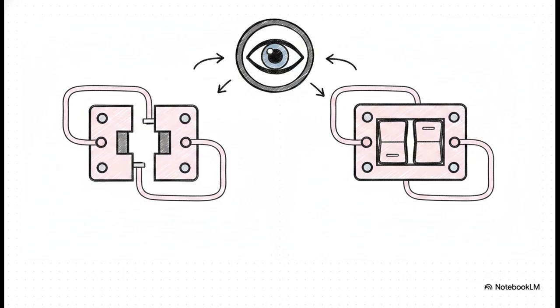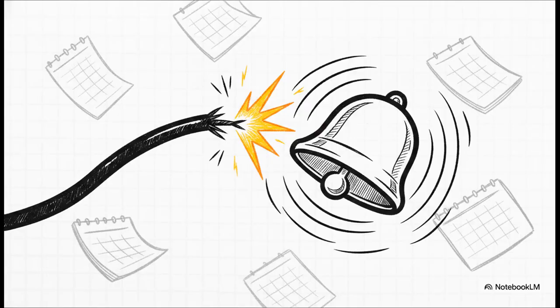TCSSCBR continuously monitors the integrity of that trip coil circuit, and crucially, it does this in both the breaker open and breaker closed states. Because the circuit topology changes depending on the breaker's position, this dual-state monitoring ensures there are zero blind spots. The RET615 relay doesn't just trust that the external wiring is okay because, well, it worked during last year's test. Instead, the TCSSCBR function runs a continuous, tiny test signal through the trip wiring at all times. It acts exactly like that little green power light on your smoke detector. It continuously confirms its readiness, so you are never surprised by a dead system at the exact moment a fire breaks out.